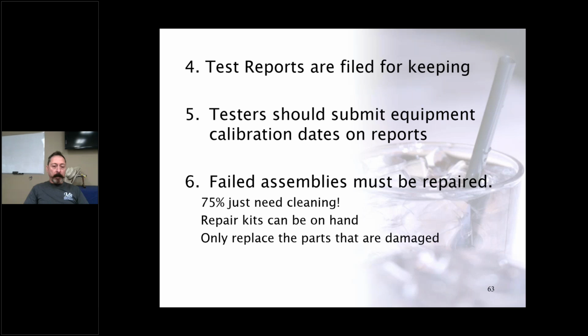Now, for remote small water operators or systems, that's often a challenge. It can take months to get a repair kit for those devices. So it's ideal that you have a repair kit on hand, because that's going to save you a lot of cost. If that person has to go back 2 hours into another community and come out a different day, they're going to charge you a charge-out rate fee and travel each way to order that kit. But if you have one on hand, that person can deal with that backflow preventer right then and there, put it back into service, do a retest, and there's no extra cost or trips.